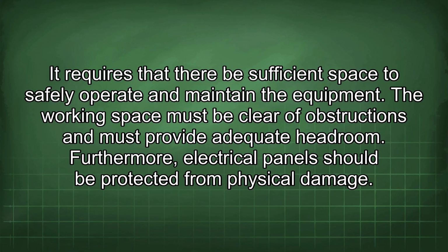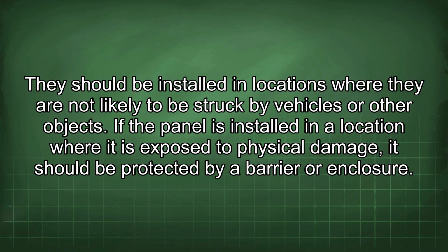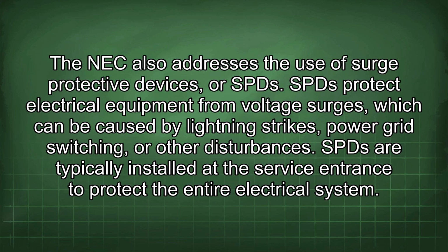Furthermore, electrical panels should be protected from physical damage. They should be installed in locations where they are not likely to be struck by vehicles or other objects. If the panel is installed in a location where it is exposed to physical damage, it should be protected by a barrier or enclosure. The NEC also addresses the use of surge protective devices, or SPDs. SPDs protect electrical equipment from voltage surges, which can be caused by lightning strikes, power grid switching, or other disturbances.